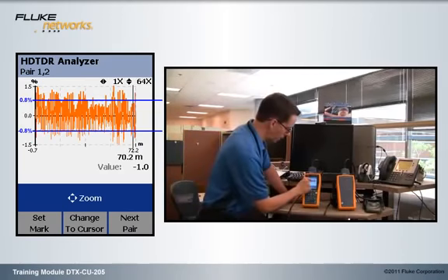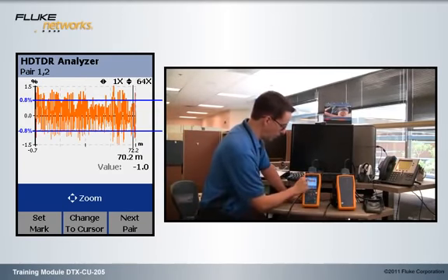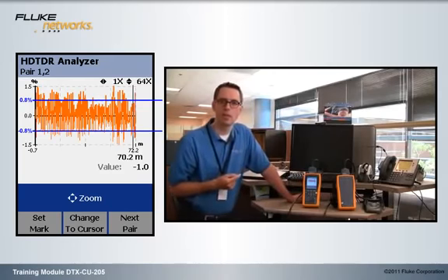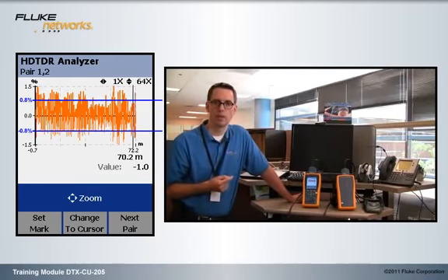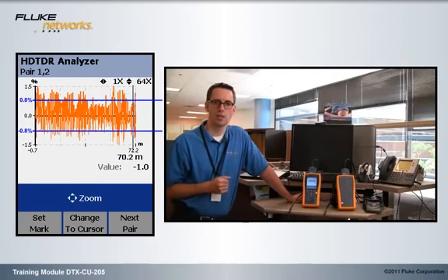Now there is a short area here where it's not too bad, but for the best part this is happening all the way down the cable, and it's only happening on one pair. Now experience tells us that if it's only happening on one pair and it's happening all the way down the cable, the installer is off the hook this time. Unfortunately it's the cable manufacturer. They had some bad cable escaped out the factory. It happens.